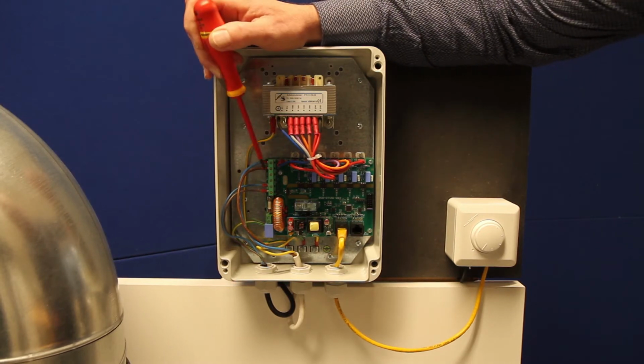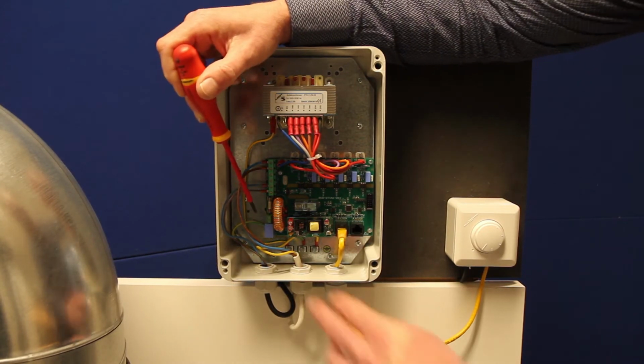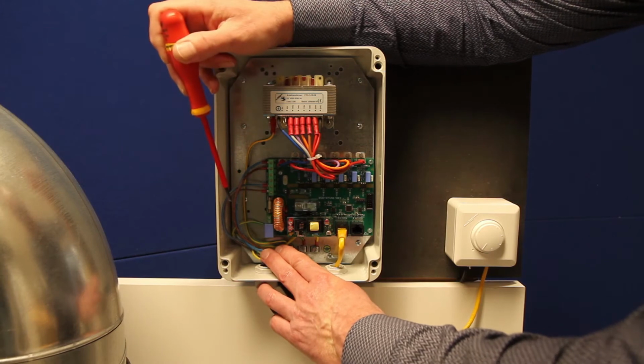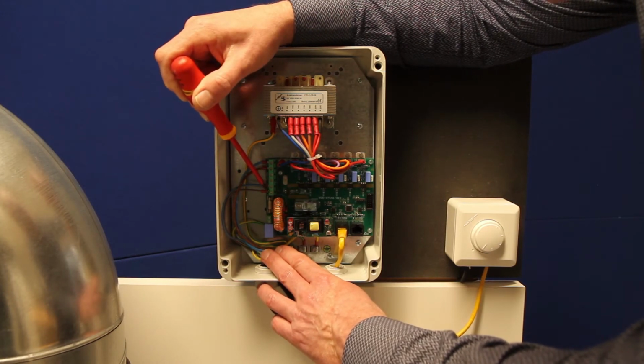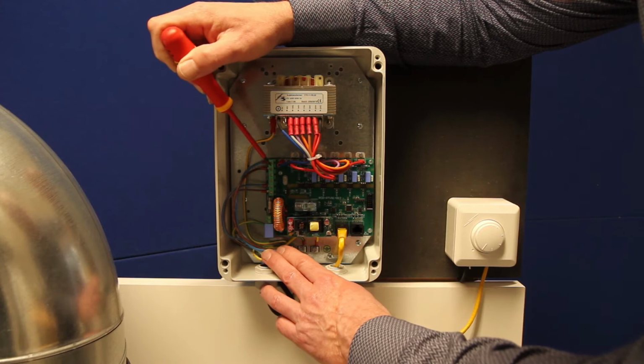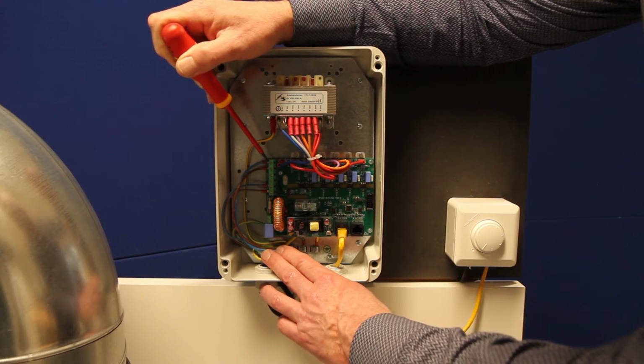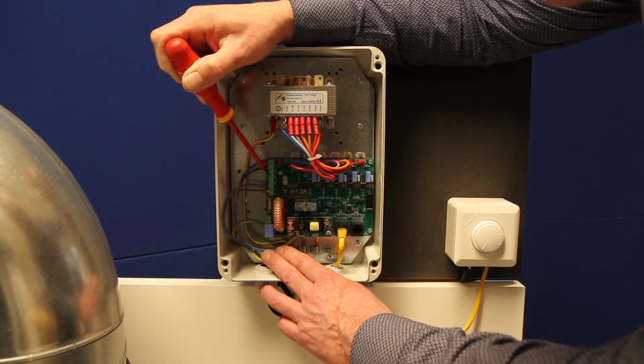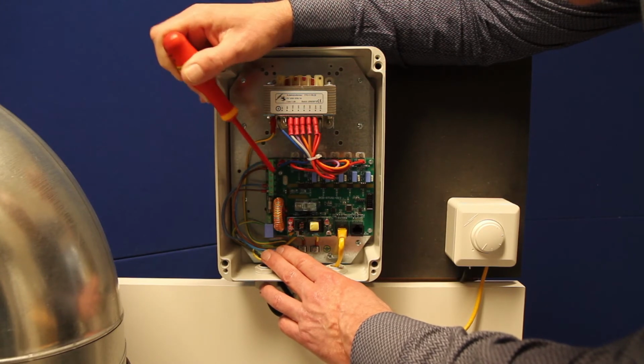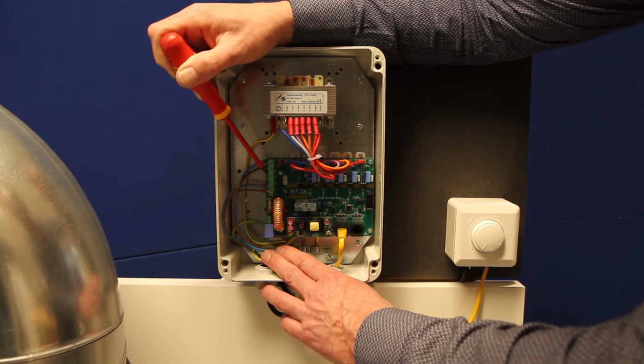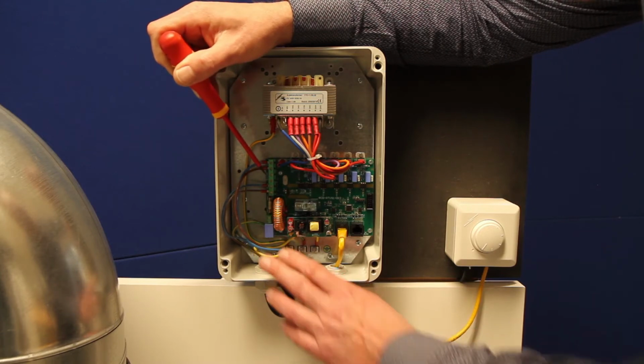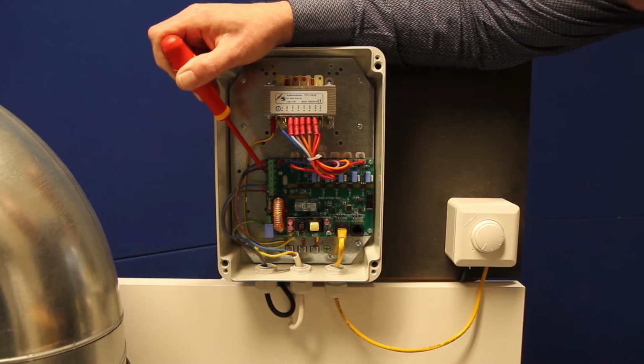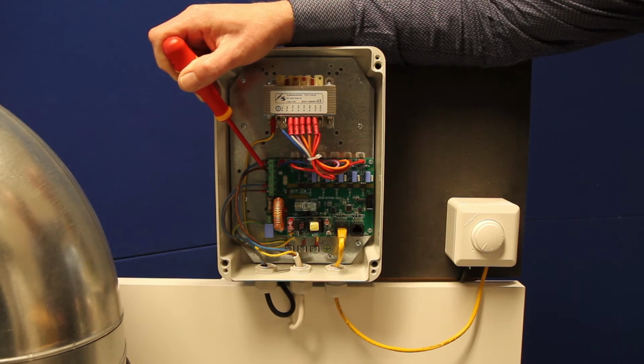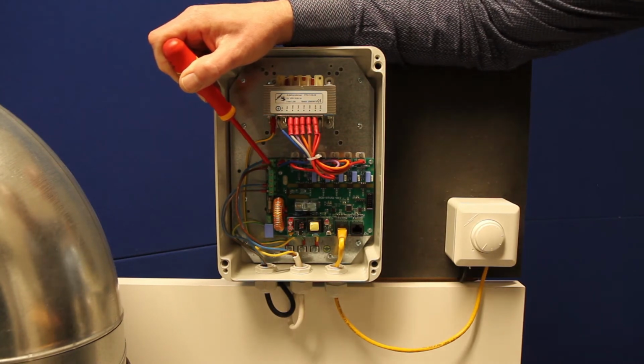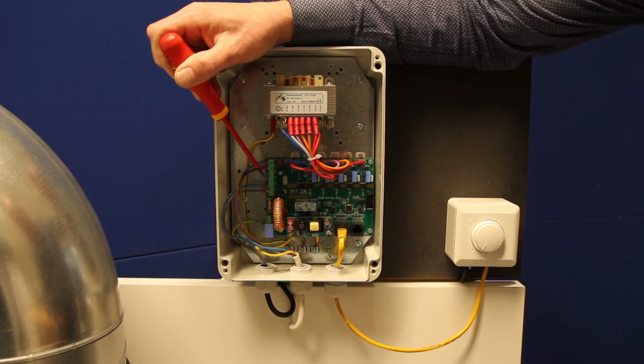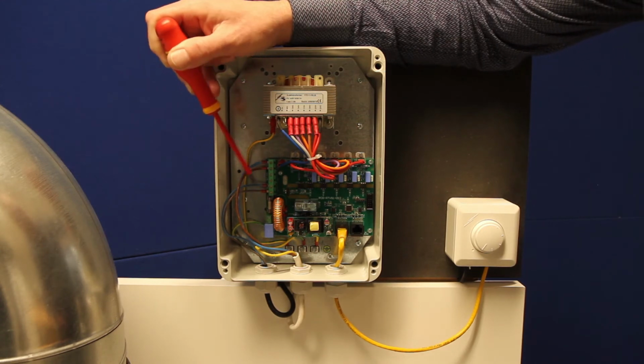On the left side of the unit, you'll notice these terminal blocks. At the very bottom, we'll see the TK connections. Just above it, we see the connections to the motor, and at the top is a 230 volt from the mains. And finally, there are the two middle connections where we find a 230 volt unregulated output. On a traditional transformer fan speed controller, 230 volts will be applied to this unregulated output as soon as the rotary knob is in positions 1 to 5 and not at the 0 position.